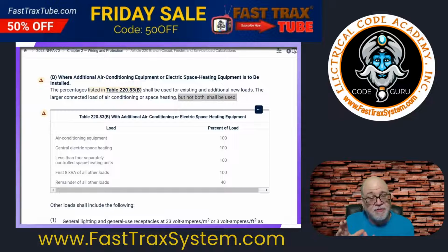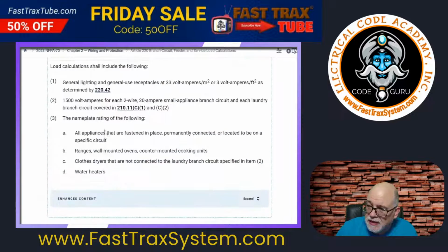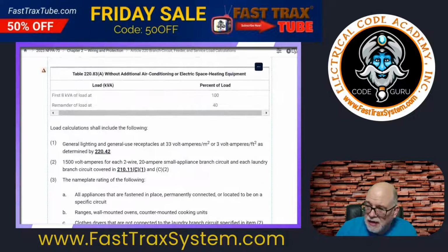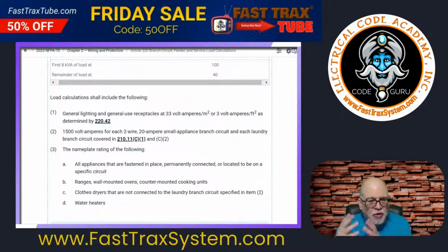And then after you get a value, then you add your AC or heat to it at 100%. All right, so that's the way you do it if you're going to add additional heating and air conditioning loads. If there's no additional, then you just follow A, and all you do is gather all the appliances, gather everything up, and gather the new stuff like EV chargers or a new circuit that you're adding for some appliance and add that in. Okay, should be simple, straightforward.